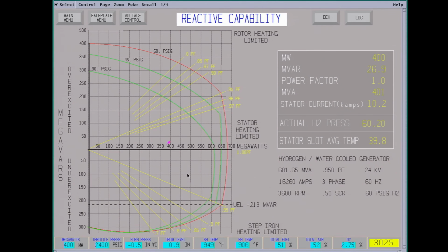This screen here is really important. This is the VAR screen showing megavars. This here is the megawatts. This here is your hydrogen pressure. 30 psi hydrogen, you gotta be in this range. 45, 60, you can run up to here. You're getting better cooling.